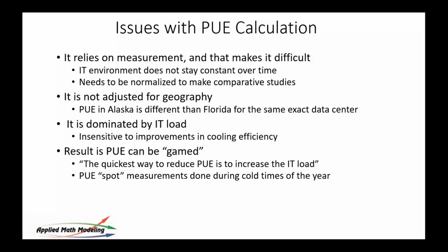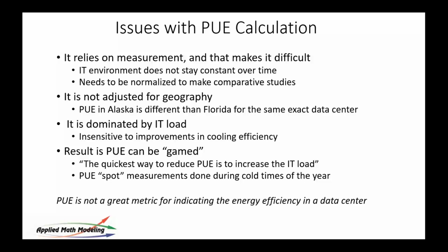I continue to go to these conferences and I hear people tell me that their PUE is 1.1, and I just scratch my head and think, what are we measuring? What does that mean? Where are we? Is it in Florida? Is it in North Pole? If it's the North Pole, just open the window, you've got a PUE of 1.0. So a lot of times these end up being spot measurements. There's no criteria really to it. The system for measuring it is poor. So it's not a great metric for indicating energy efficiency in a data center.